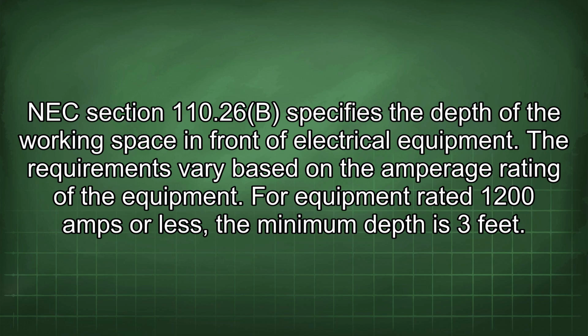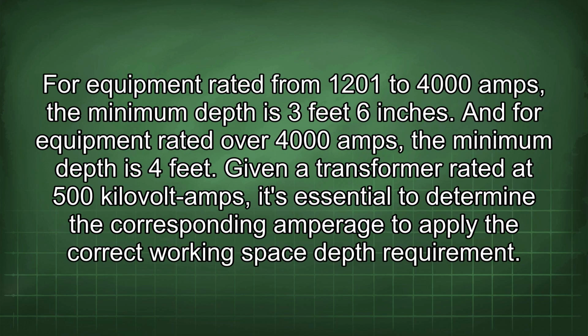The requirements vary based on the amperage rating of the equipment. For equipment rated 1200 amps or less, the minimum depth is 3 feet. For equipment rated from 1201 to 4000 amps, the minimum depth is 3 feet 6 inches. And for equipment rated over 4000 amps, the minimum depth is 4 feet.